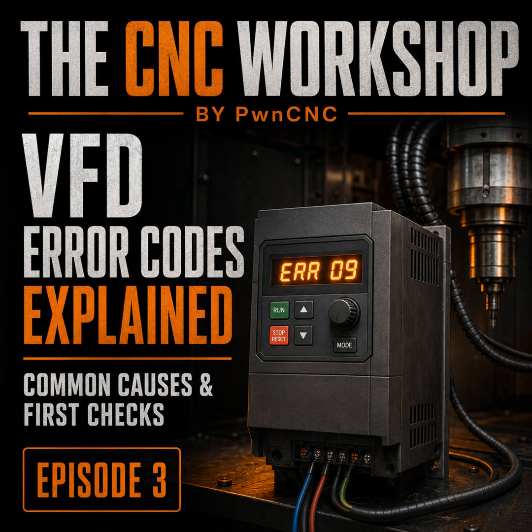Second example. The spindle warms up without an error, but ERR12 appears as soon as the gantry travels to the far end of the machine. Inspect the moving spindle cable, drag chain capacity, bend radius, and connectors before changing parameters. Third example. ERR31 returns while the spindle is running unloaded. Stop repeatedly resetting it. Inspect the cable, grounding, connections, and spindle condition. Then arrange for the VFD or system to be evaluated.